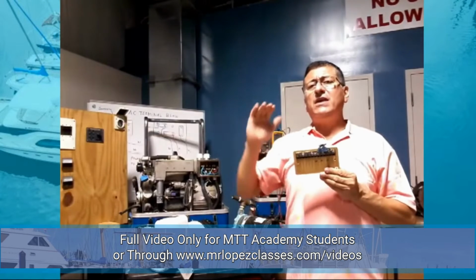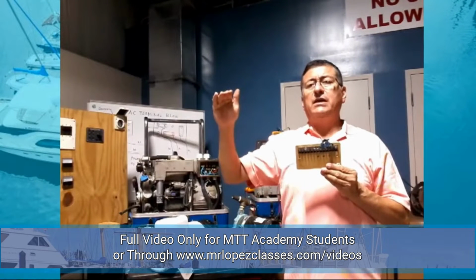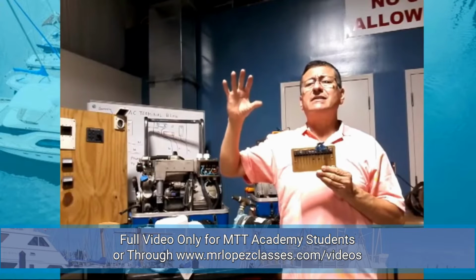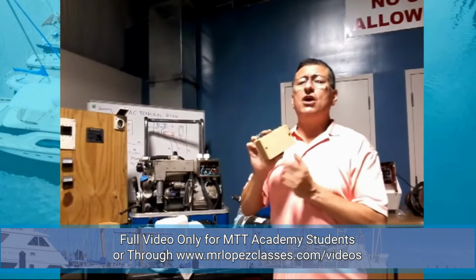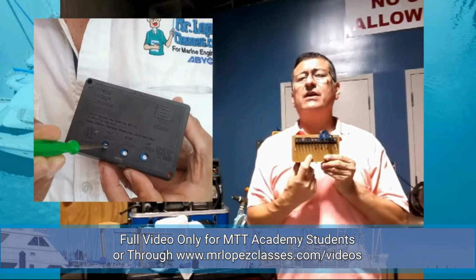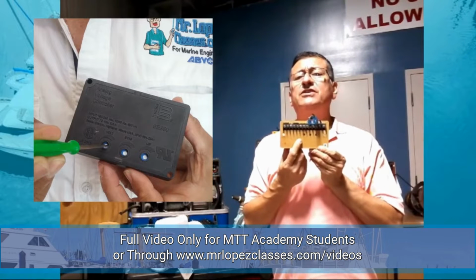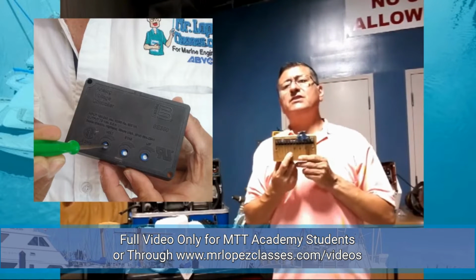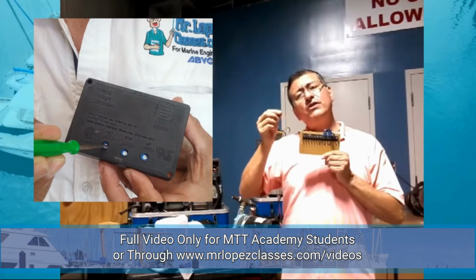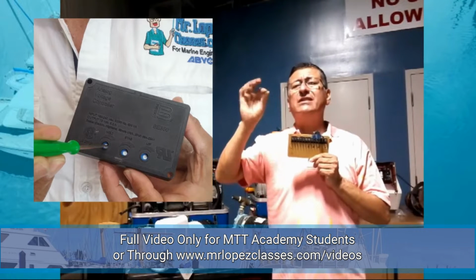This is the voltage regulator. If the increment or decrement is more or less 10%, you can adjust with a small screwdriver in the first spot. The first spot is volts. This is to calibrate high voltage or low voltage if the increment is no more than 10%.